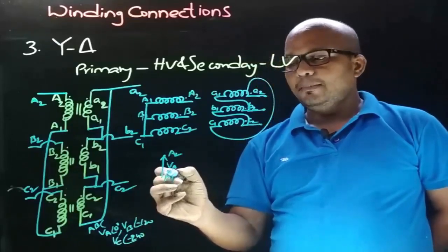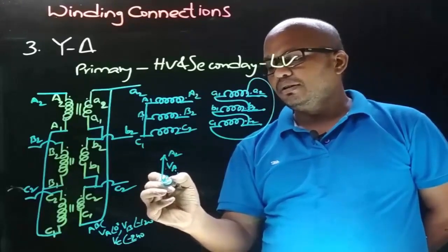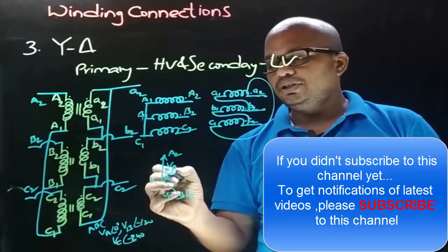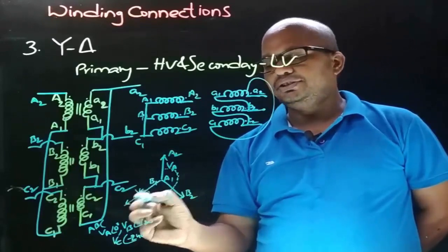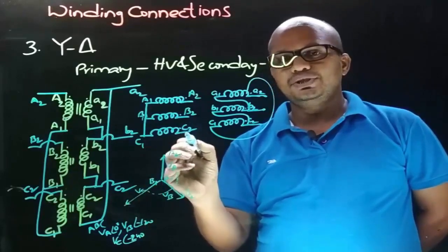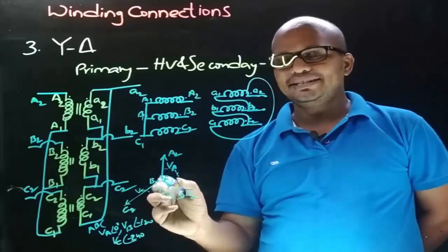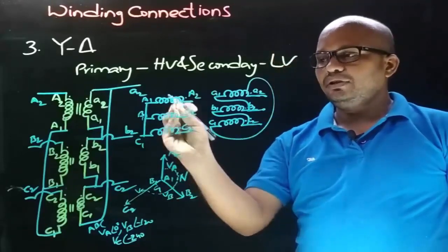VB will be at -120° from VA, so in the clockwise direction at -120° we will have VB. The terminals of VB phasor are B1 and B2, and as B2 is the connection taken from, the arrow points towards B2 and the other end is B1. At -240° from VA, draw VC phasor. The terminals of VC are C1 and C2; as C2 is the connection taken from, the arrow points towards C2 and the other end is C1. Capital A1, B1, and C1 form the common neutral terminal, represented as capital N. We obtain the phasor diagram for primary winding connections.